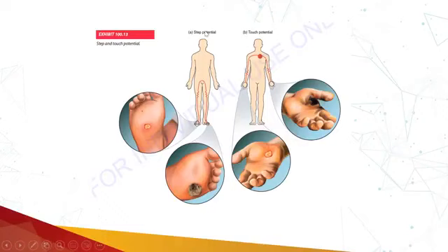So what is the step potential? Step potential is the type of electric shock in which current is going to enter through one leg and exit through the other leg. So it's an entry point and an exit point of the current passing through the body. Any other combination of current entering into the body and passing through it will be covered in the touch potential. For example, from hand to hand, from hand to feet, from head to feet, or any other combination. All those combinations are considered as touch potential.